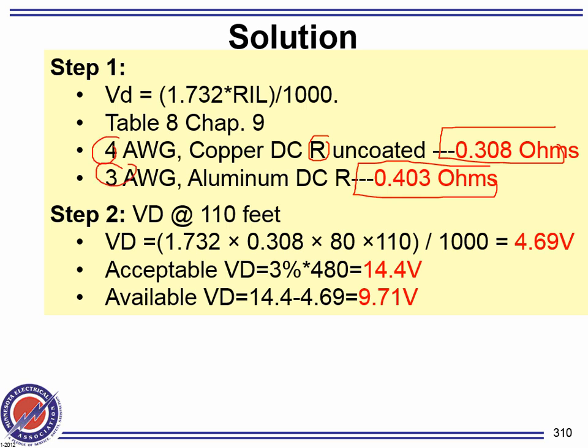You need to go to the table to find the R for the two cables. Once you find the R, then the voltage drop at 110 feet away from the panel, piece of cake. Here's your 1.732. Here's your 0.308 voltage drop, or I'm sorry, impedance. 80 amps, the length is 110, so you have this amount of voltage drop. At the current location, we lost 4.69 voltage drop.